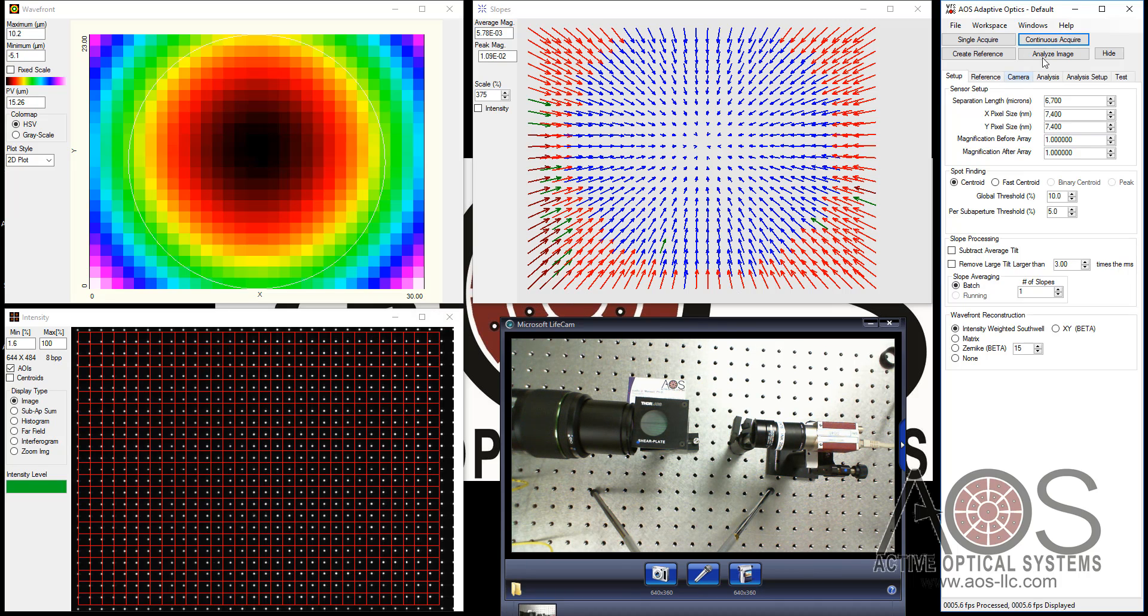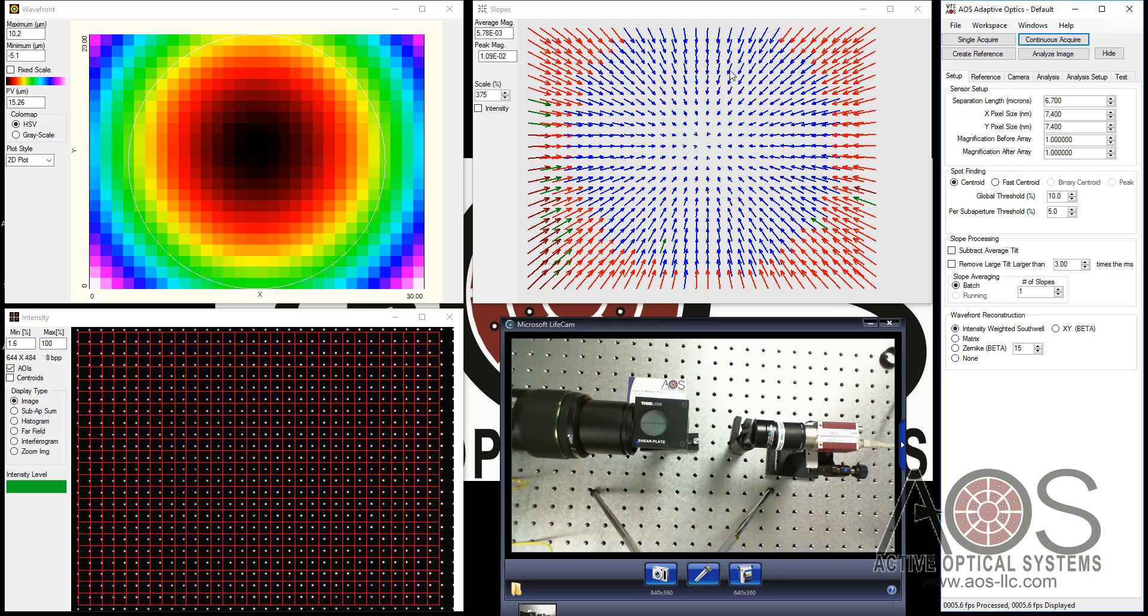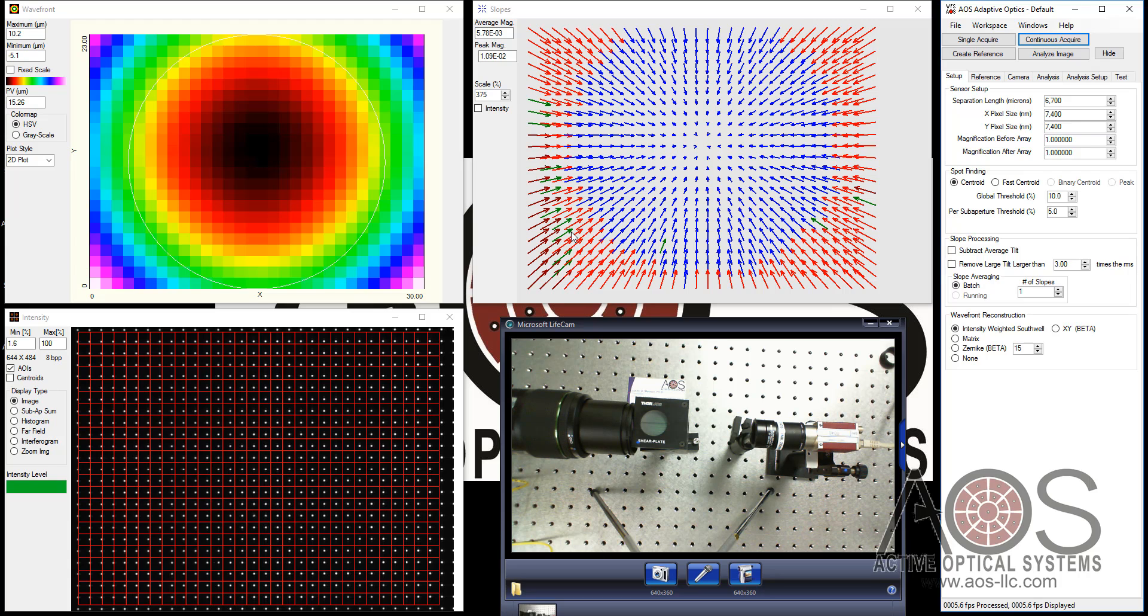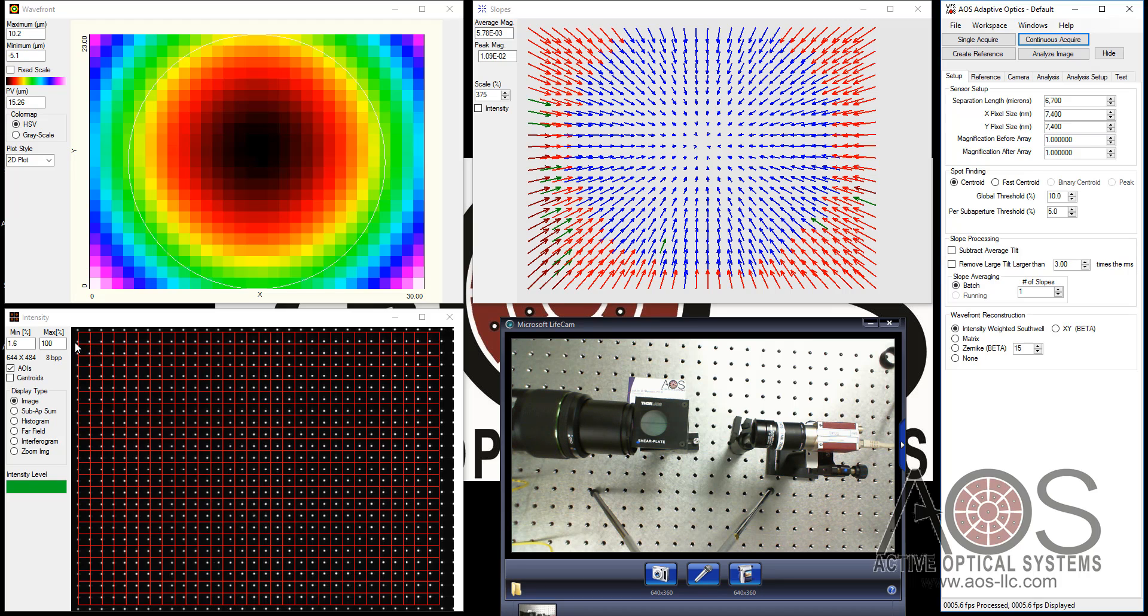The interesting thing about putting a 300 in is that we are getting very close to the dynamic range of the wavefront sensor. And so what you can see happening in the slopes is that a lot of these slopes are reporting as blue or acceptable. Some of these are starting to get into different colors, reds and greens. And this has to do with different variants on being an unacceptable slope measurement because the spots are getting too close to the edge of the AOIs or actually falling outside the AOIs.